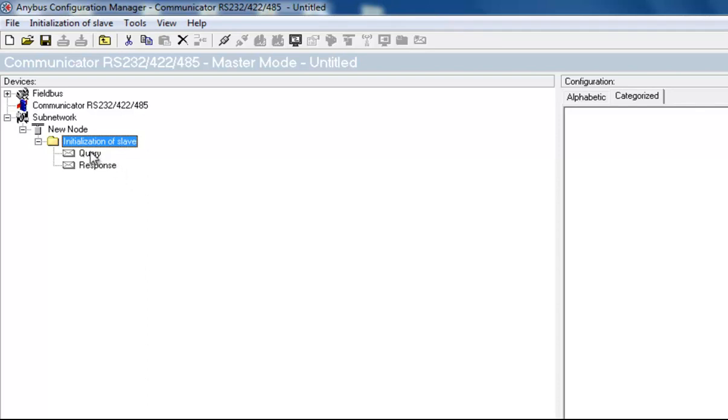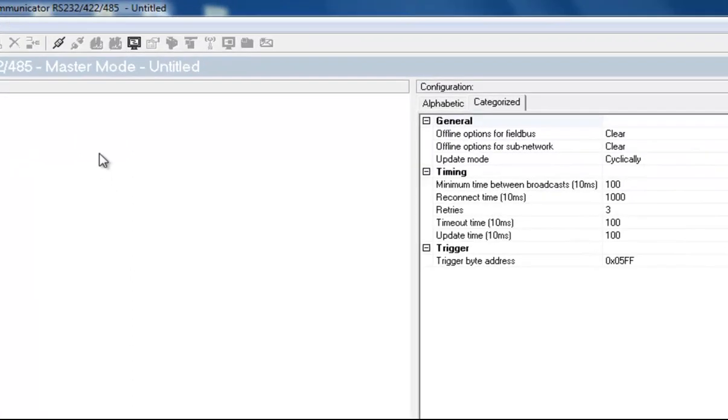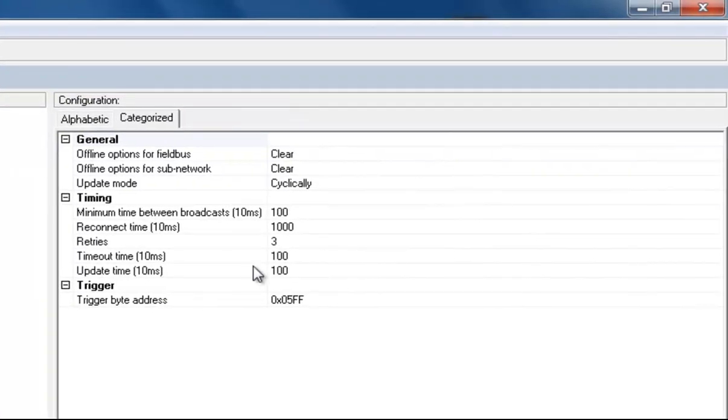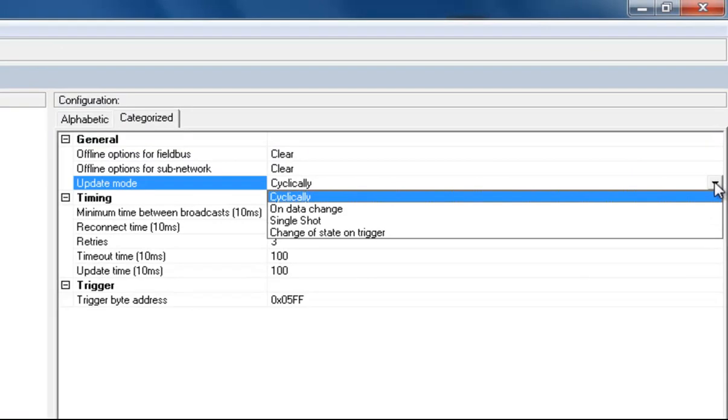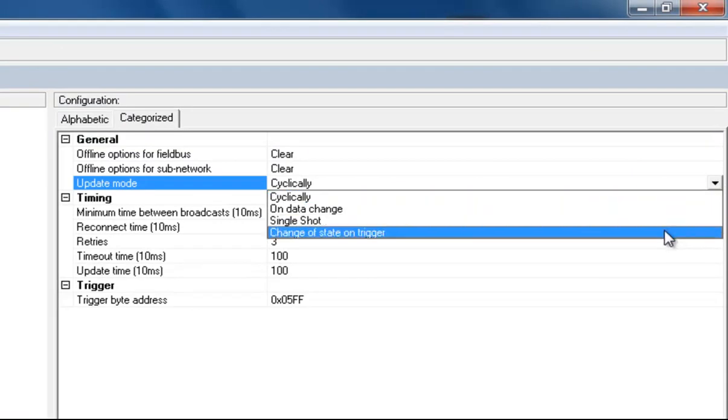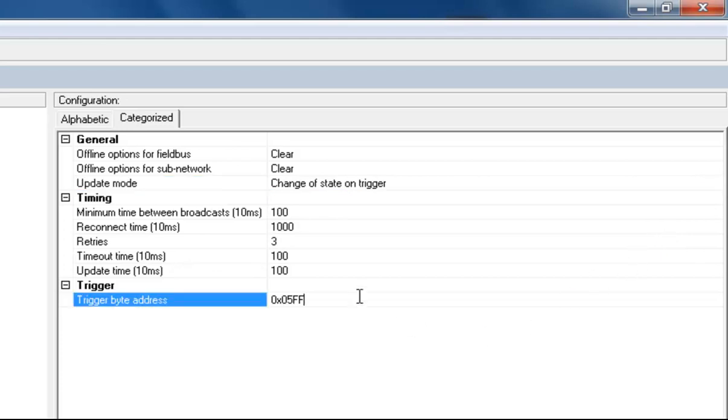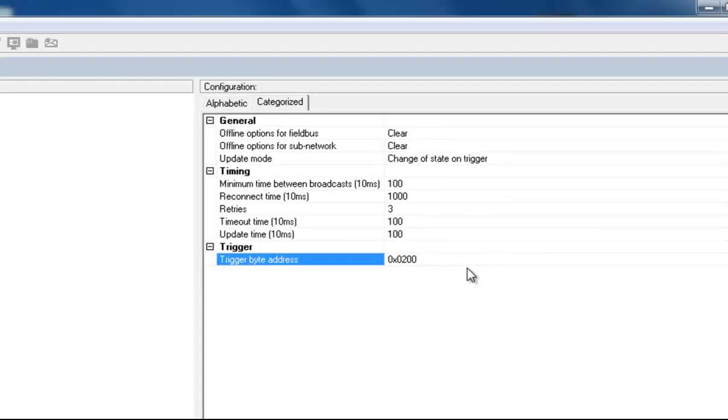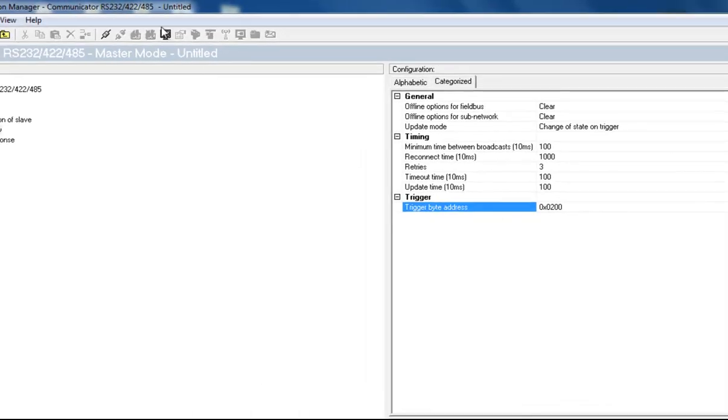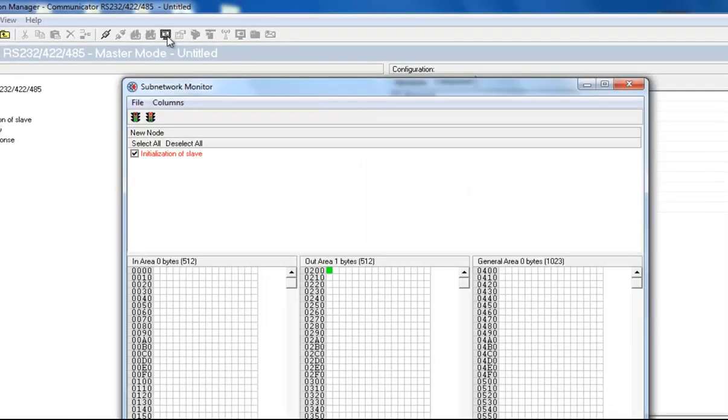In the query to the energy meter, I set the update mode to Change of State on Trigger, so that the PLC on the Profibus side decides when it's time to initiate the slave. We set the trigger byte to address 200. If I open the subnetwork monitor, I can see that this is the first byte in our out area.